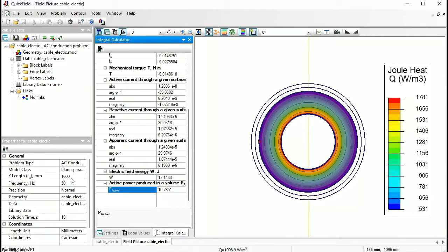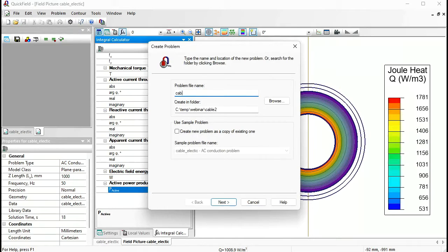Remember, this cable is energized. It is connected to the voltage source, but the load is not connected, so there is no electric current in the conductor, and the only losses in the cable are dielectric losses. The cable is kept energized for many hours, many days, and our task is to calculate the steady state temperature of the cable. So next I'm going to simulate the thermal problem. File, new problem. Cable heat.